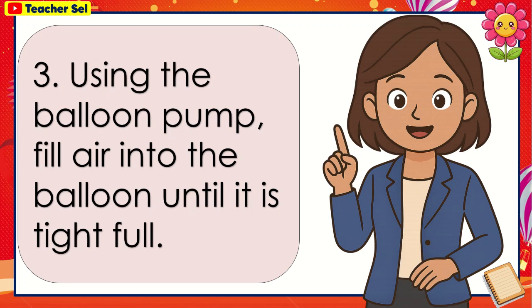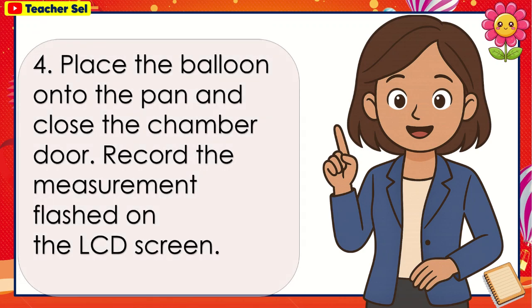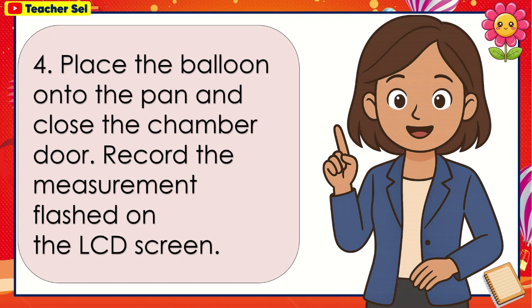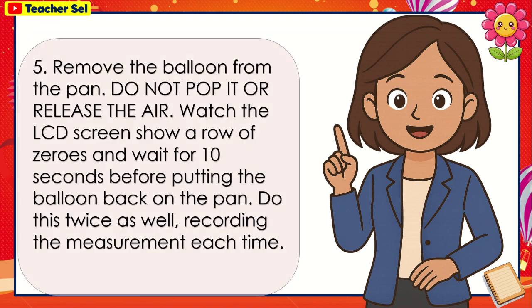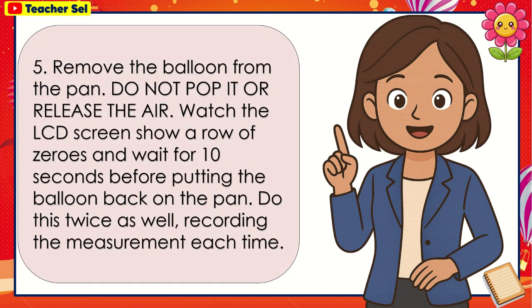Using the balloon pump, fill air into the balloon until it is tight full. Place the balloon onto the pan and close the chamber door. Record the measurement flashed on the LCD screen. Remove the balloon from the pan. Do not pop it or release the air.